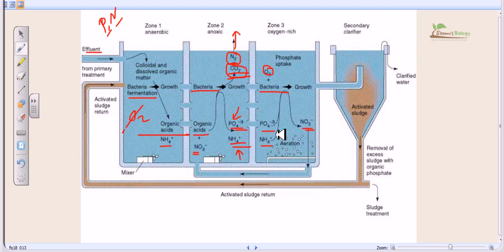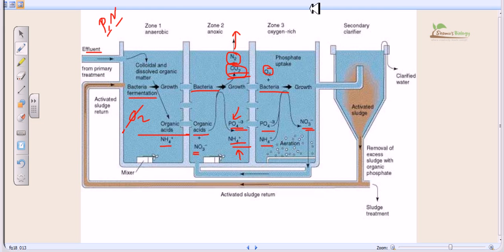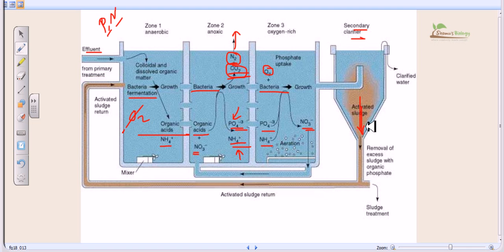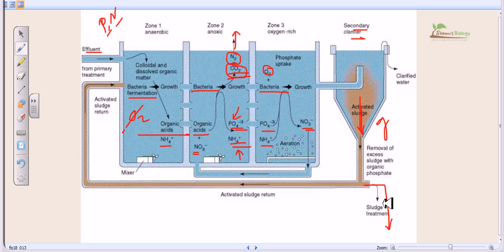A third type of bacteria can utilize only phosphate and ammonium content, converting them into nitrate, growing on these nutrients. The bacteria are happy because they have sufficient nutrients, and we are happy because our goal is achieved. After all treatment — aeration basin or anaerobic treatment — the effluent goes to the secondary clarifier, a large basin where, due to bacterial activity, small particles clump together into large aggregates and sediment out under gravitational force, forming sludge.